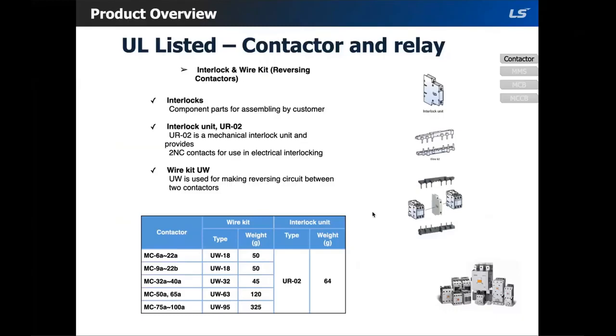So if you need a reversing contactor, you would need to order two contactors plus an interlock unit and a wire kit. The wire kit only goes up to 100 amps, so anything above that, you would have to manually wire it. The wire kit product code is the UW. Depending on the size of the contactor, you would select a UW 18, 32, 63, or 95. And then the interlock unit from this range, 6 amps to 100 amps, would be the UR-02.